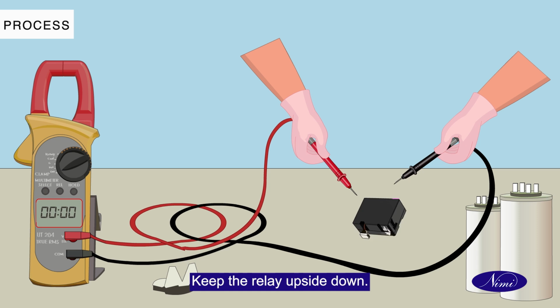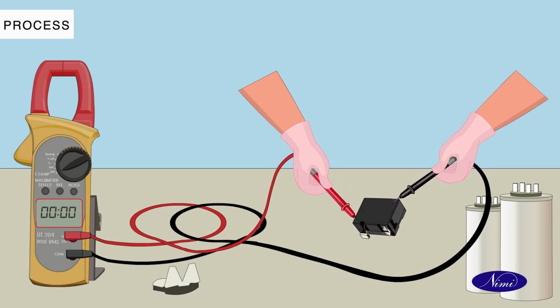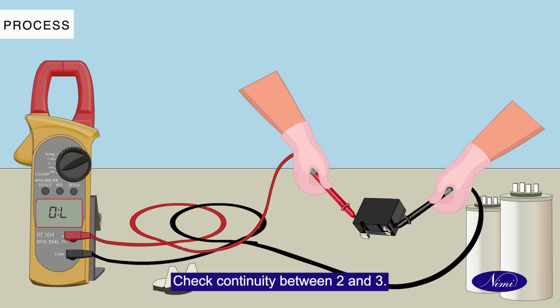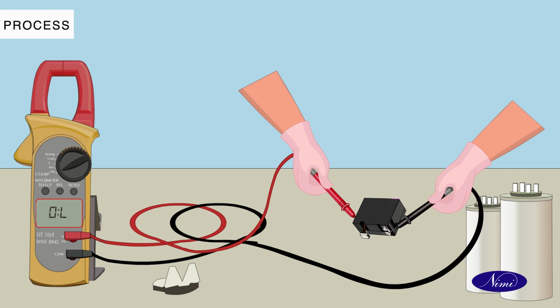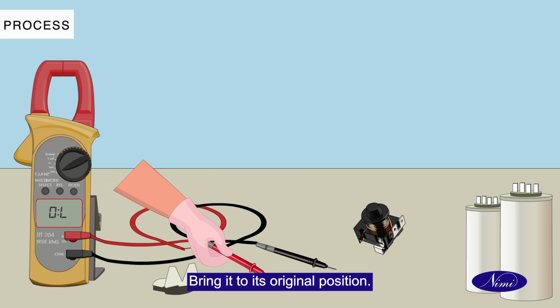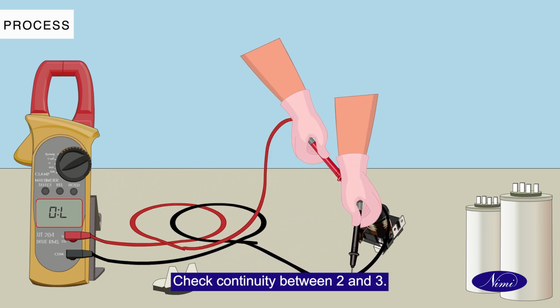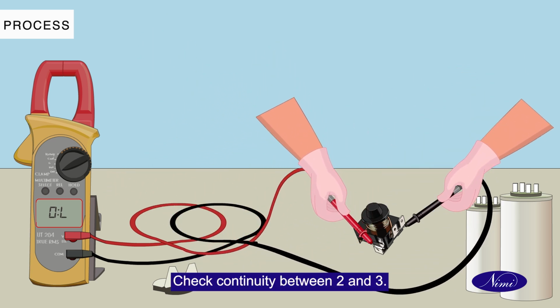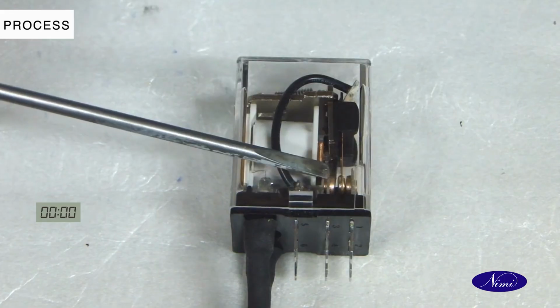Keep the relay upside down. Check continuity between 2 and 3. If the continuity is there, the relay is okay. Bring it to its original position. Check continuity between 2 and 3. If there is no continuity, the relay is found OK.